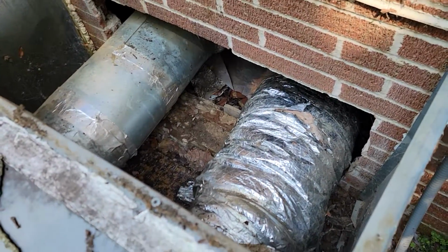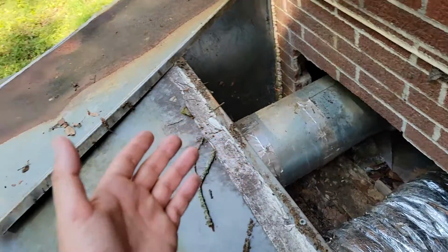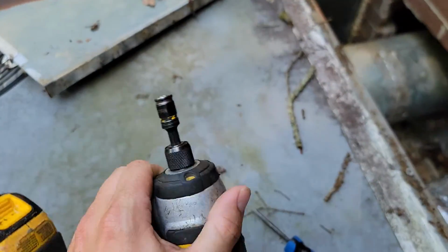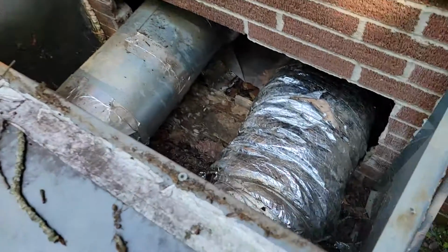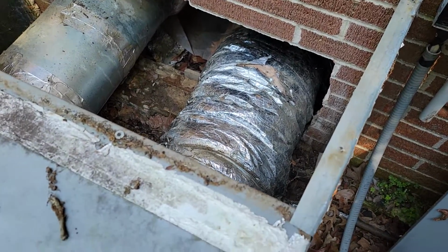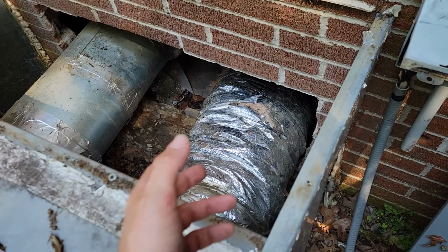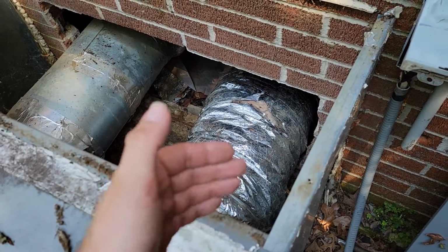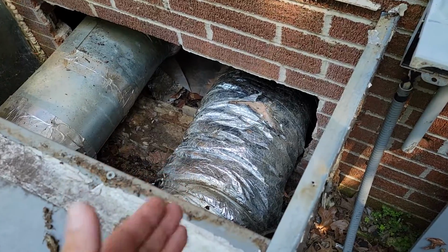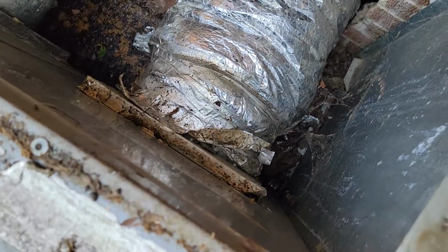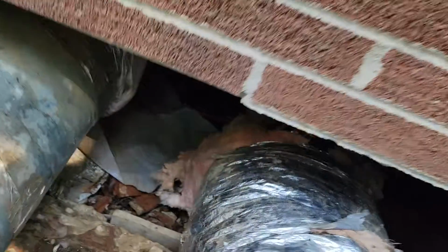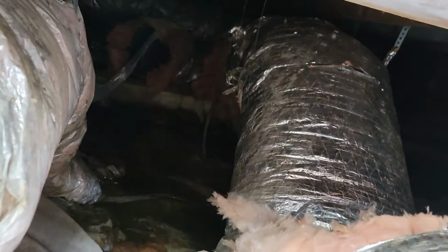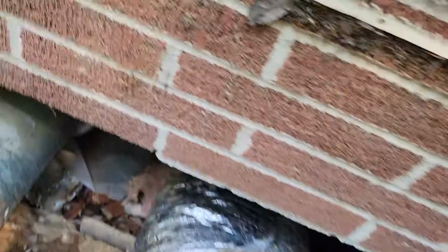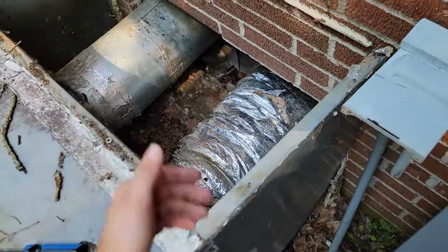Whee! Just want to do a video because I don't run into this very often. But I was like, wow. All you have to do is have your little driver, your little 1/4 inch. Take your zip screws loose. Looks like I'll need to get a coupling. The way I'll fix this is I'll of course offer new ductwork, but I'll also go ahead and try to get it repaired because it's really hot in the house. So probably bring back some 12-inch pipe, and then I'll make a coupling there. If the flex is not deteriorated. If it's deteriorated, then no, I'm gonna be making sure I fix this the right way. But yeah, we got a ductwork problem.